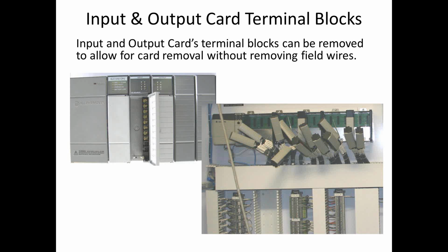So there are a variety of ways of getting this data to them. The upper left-hand picture on your screen shows a terminal card, and you could wire your instrument directly up to that terminal card if you needed to. The problem is that if you needed to take that card out, you would need to undo all the wires, and then you need to be responsible for making sure they were wired correctly back. And with all those field wires going into the terminal cards, you can get quite a cluster, which is what you see on the right-hand side of the picture. It's kind of a mess.